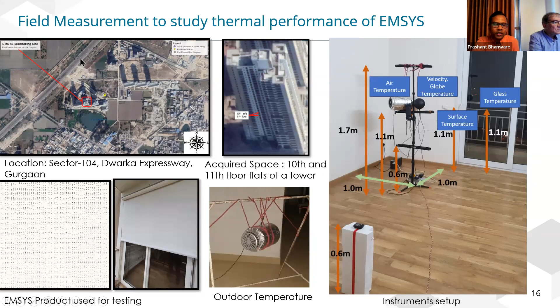This graph shows the naturally ventilated mode, which means the air conditioning was off. The windows were open during the night time for ventilation purpose, and during the daytime the windows were closed. In case of EMSyS, it was down during the daytime, and in the other case, it had internal curtains which were on during the daytime. The red graph shows without EMSyS, or with internal curtain, which is the normal practice, and the blue one shows the operative temperature with EMSyS.